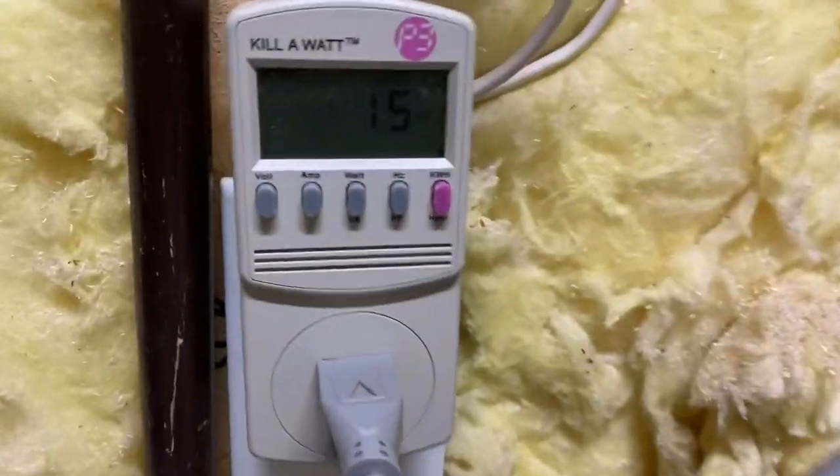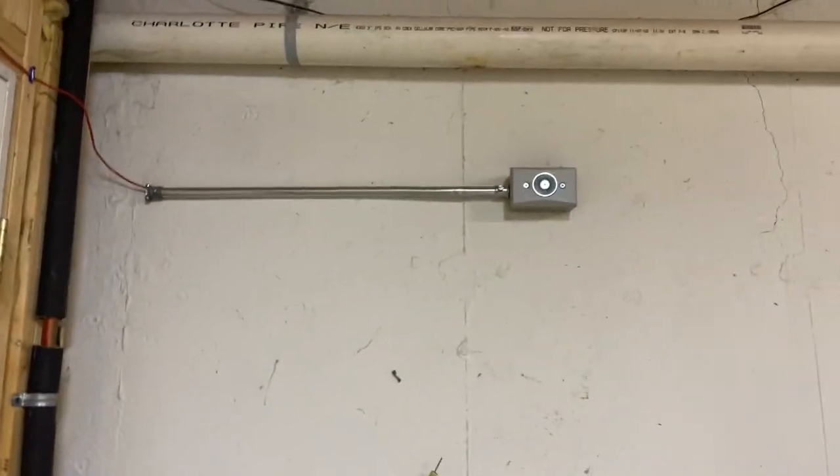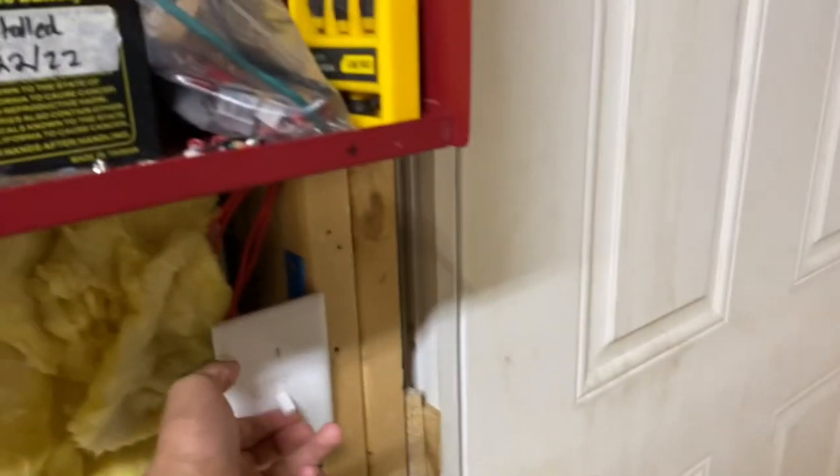I've just connected the fire panel to the Kill A Watt — it's reading 15 watts, which is pretty decent because obviously nothing's happening. So let's turn that magnet on. Right now there's nothing attached to the magnet, and it's still at 15 watts, so it doesn't look like that magnet is really drawing anything yet.